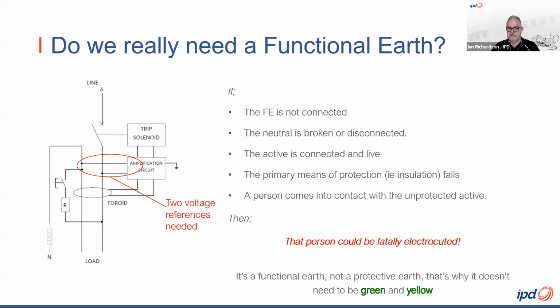You know, Fred, I've even had some people tell me that they cut off the functional earth conductor, and it's really a misunderstanding of why it's there. But as Fred has explained, the functional earth is there as an additional safety for some voltage-dependent RCDs. So guys, please use it. Don't snip it off. It's there for a very, very valid reason in case the neutral gets damaged.